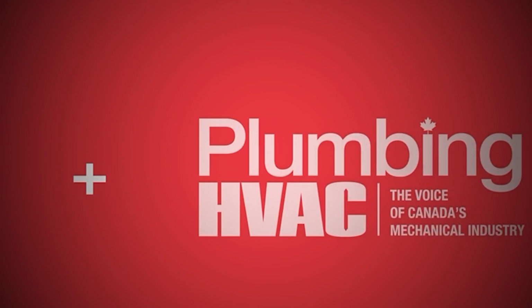We've got an extensive set of technical literature to help. We've got a 4-page commissioning checklist to go along with our extensive training curriculum. But when the contractor brings this out, you're right. He's going to need 115 volt, 7 amp of power. Typically, depending upon the length, a 1/2-inch gas line. So there's no upgrade there.